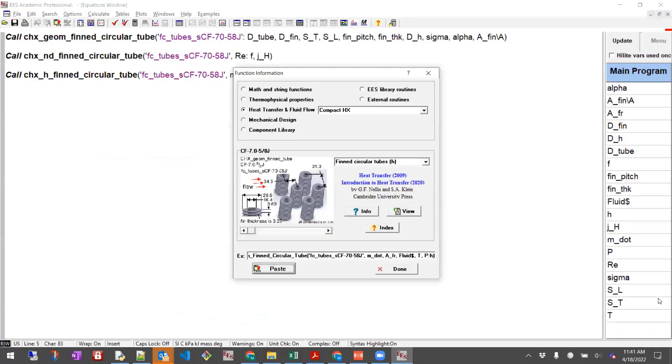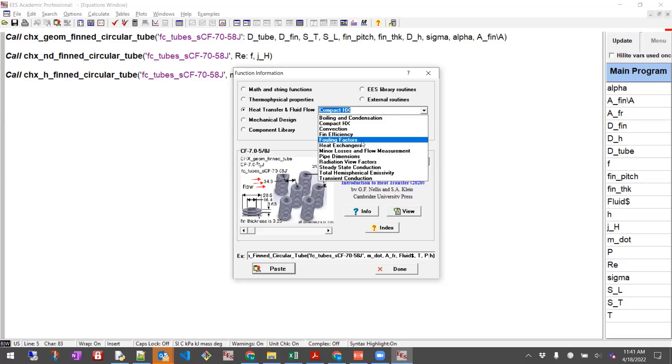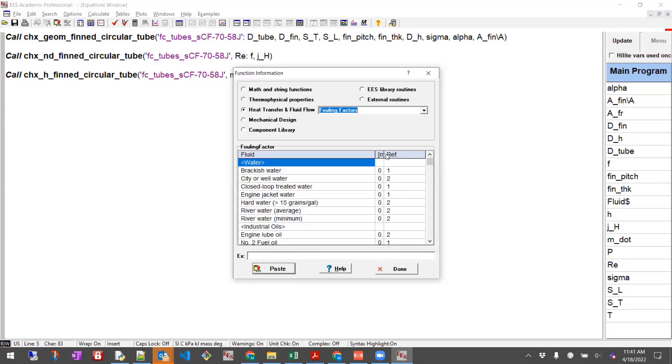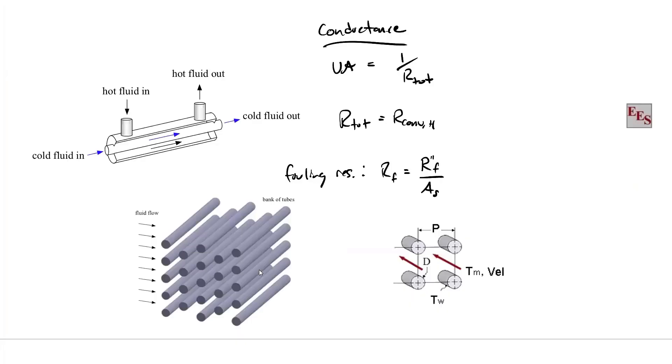So we have our fouling resistance. That's defined as R sub F is normally given to us as R double prime F, and then we divide that by the surface area that's available. R double prime F is something we can go look up and use usually. If I look in my library here, there's a dropdown that says fouling factors. I could go into this table. It's not formatted very well, but I could say is my fluid water? My fluid's water and it's brackish water, city well water, river water, whatever. I can come in here and I can paste this thing in. That's going to return for me a small number, usually like one e to the minus four or something like that.